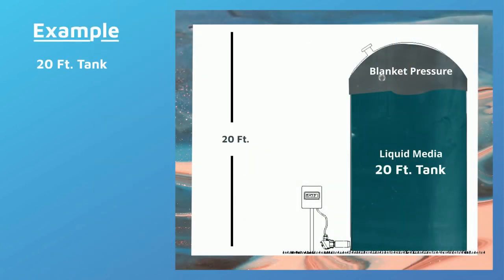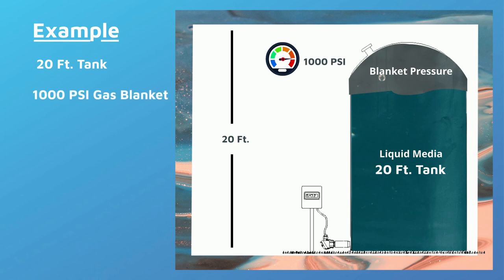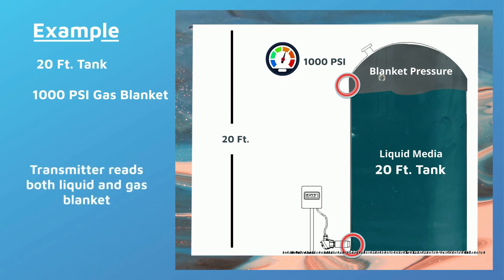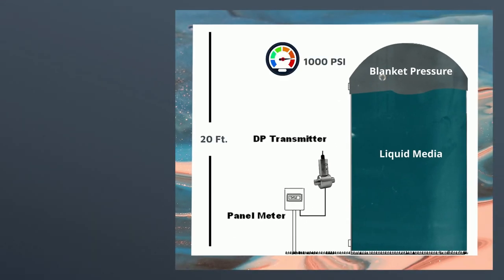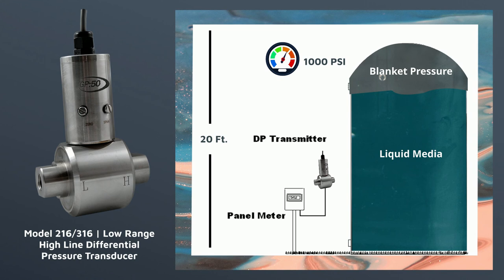For example, if a tank is 20 feet tall and there is a 1000 psi pressurized gas blanket on top, putting a hydrostatic level sensor at the bottom of the tank would measure the 20 feet of water column as well as the 1000 psi of blanket pressure, giving you a combined pressure of both the liquid and gas blanket. In order to subtract the gas blanket pressure from the liquid level pressure, you need to know the gas blanket pressure. To do this you can use a differential transmitter and plumb the high side to the bottom of the tank and the low side to the top where the gas blanket pressure is located.